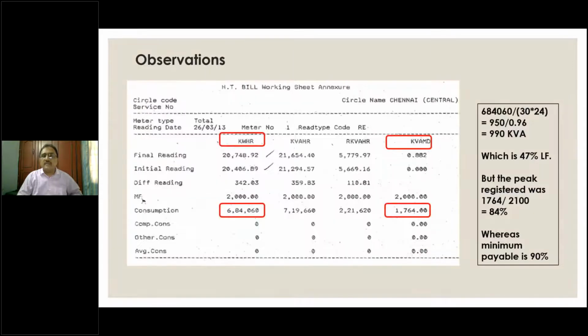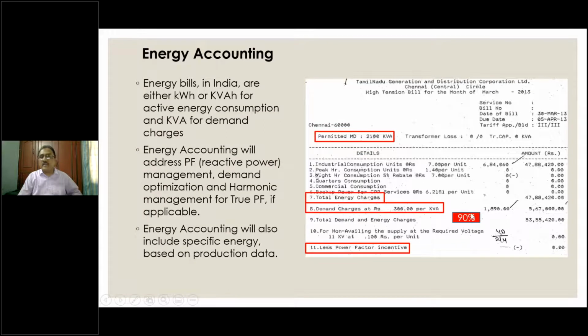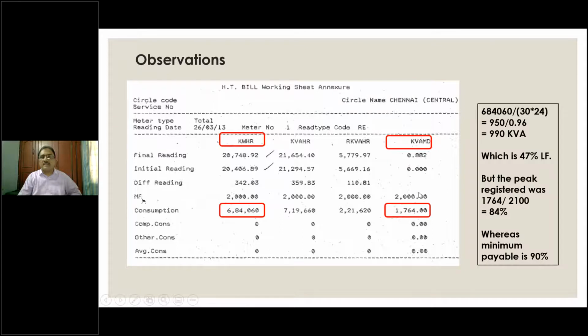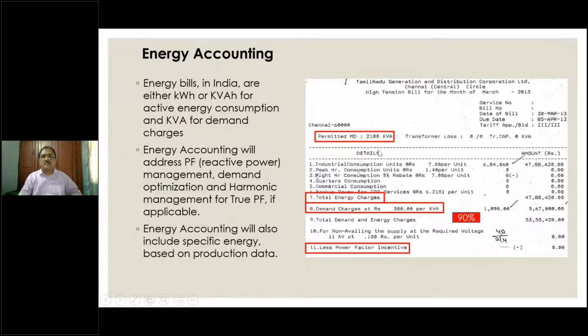So this is 90%. If you come back again, if you come to this slide, you will notice that actual demand reached is 1764 only. See here, the kVA demand reached is 1764, which is 84%. Now they are still paying 90. So anything more than 90, they will pay actual. If it is 91, 92, 93 or 95%, they will pay actual. But anything below 90, they will have to pay minimum 90% of the contract demand. So this is one factor. Is it possible for them to surrender demand such that they bring this 1764 below 100 or above 90? So that is the expectation. This is the expectation from the bill.